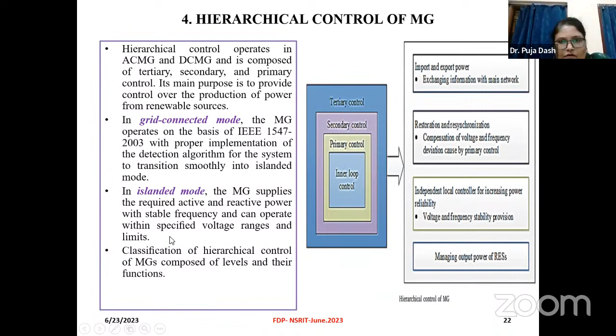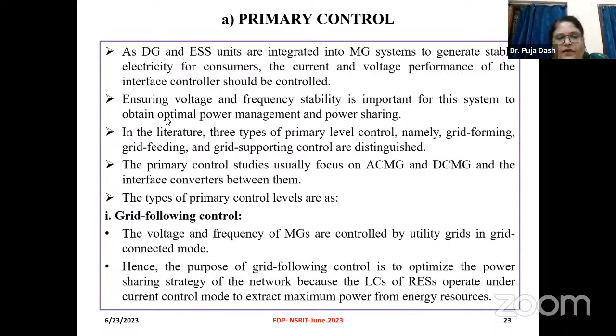So generally, what happens in grid following mode? The voltage and the frequency of the microgrid are controlled by the utility grid in grid-connected mode. So the purpose of grid following control is to optimize the power sharing strategy of the network, because the local controllers of the RES operate in current control mode to extract the maximum power from the energy sources. And when we talk about grid forming mode, that means the microgrid is operating in islanded mode. An optimal active and reactive power control should be realized to provide adequate power and frequency sharing between the DG and ESS, the energy storage units, and to regulate the best frequency of the AC. This is called grid forming, and there are two configurations: single grid former and multiple grid formers.